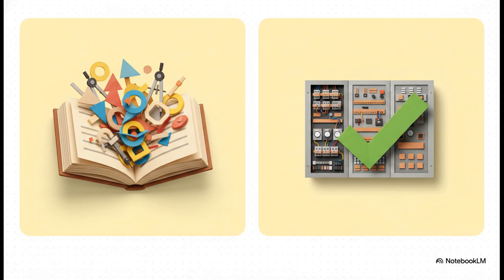Basically, think of 60664-1 as the textbook that teaches you the math and 61439 as the final exam verifying your assembly actually passes. Oh, and a quick note from the sources. A standard insulation Megger test is not an acceptable substitute for clearance verification under 61439. You need dedicated power frequency or impulse-based methods for that.